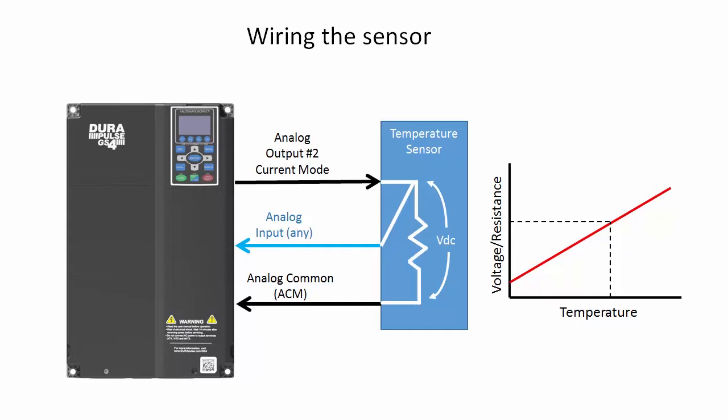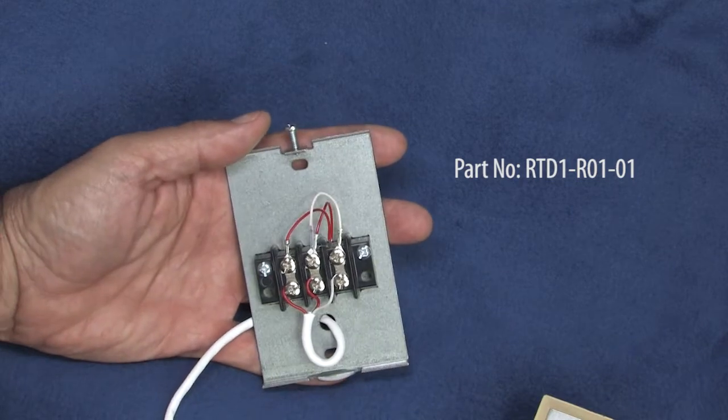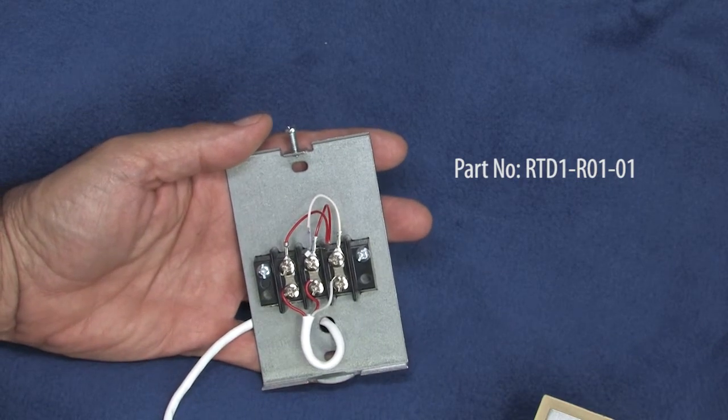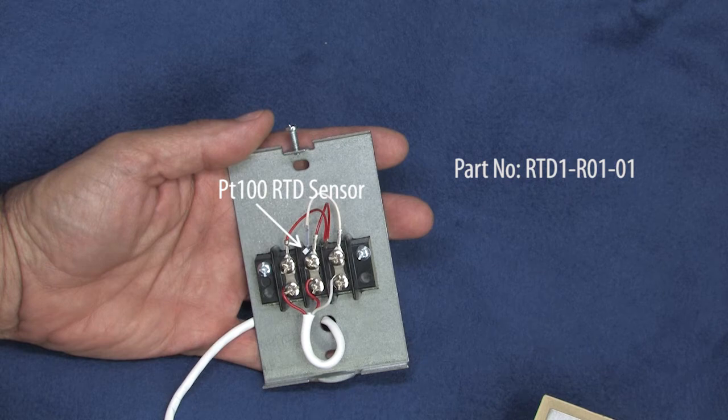By the way, could you drive this sensor with your own current source? Sure. You might want to do that if you are already using analog output 2 for something else. But in general, using the GS4's current output feature is so easy and convenient, there's usually no need to spend the extra money on an external supply. I'm using the RTD in this room temperature sensor from AutomationDirect simply because that's what I had laying around, but any PT100 RTD will do.